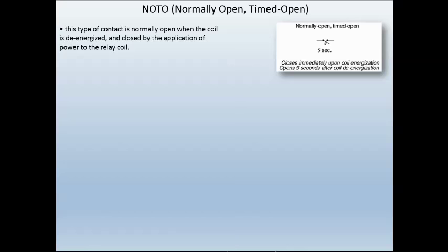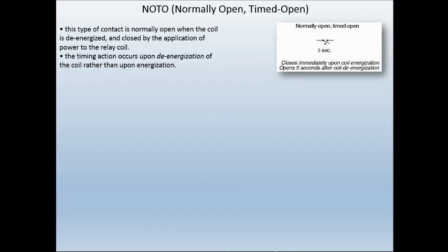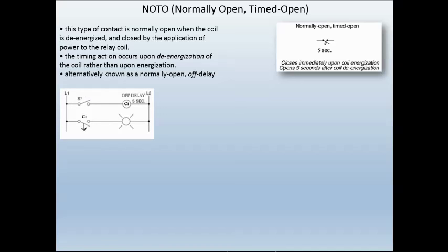Now we have a normally open timed open. Here's the symbol for the normally open timed open. This type of contact is normally open when the coil is de-energized, and closed by the application of power to the relay coil. The timing action occurs upon de-energization of the coil rather than upon energization. This is alternately known as a normally open off delay.